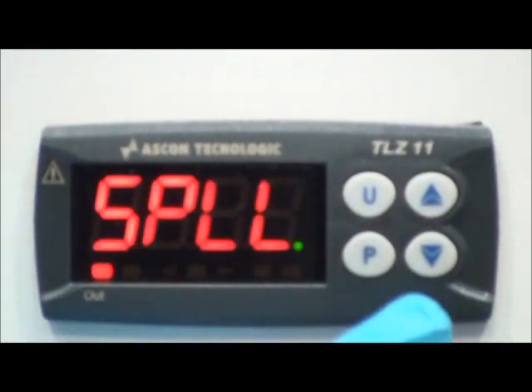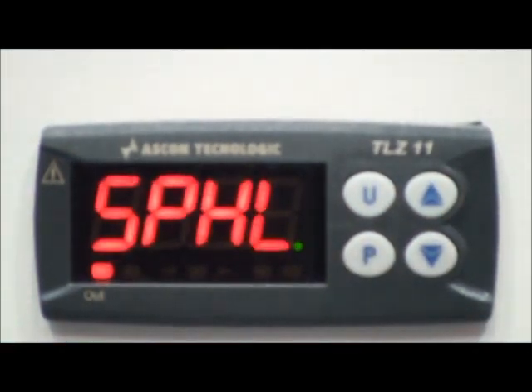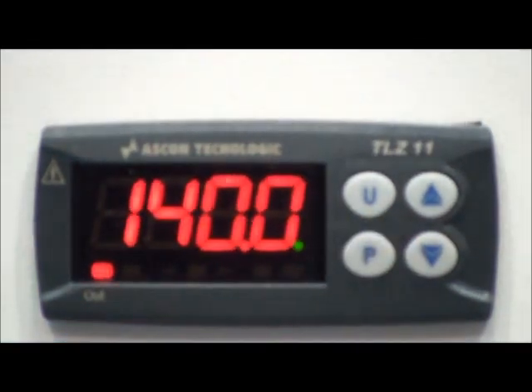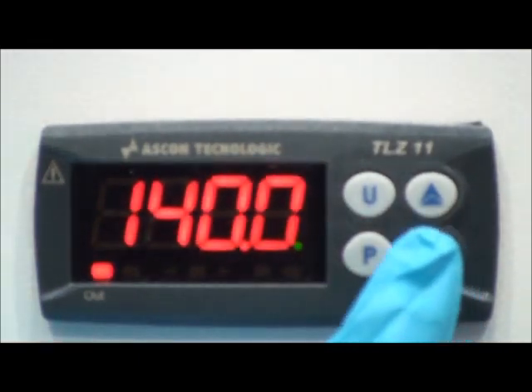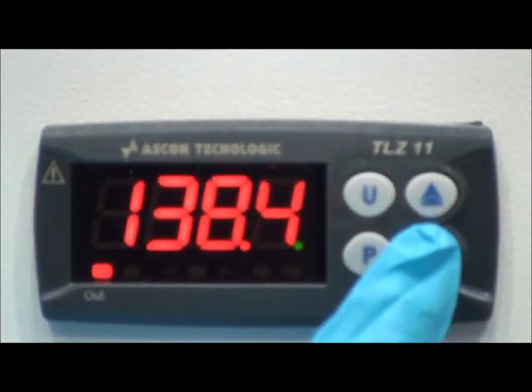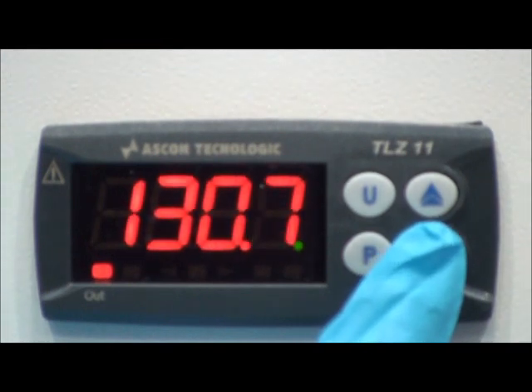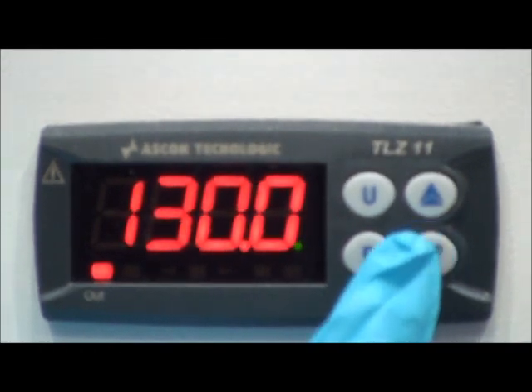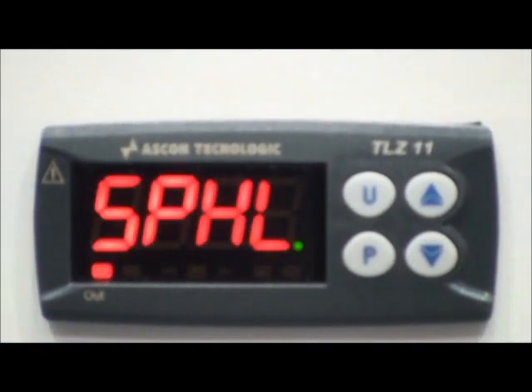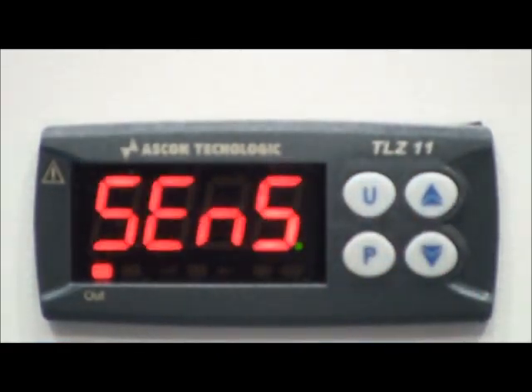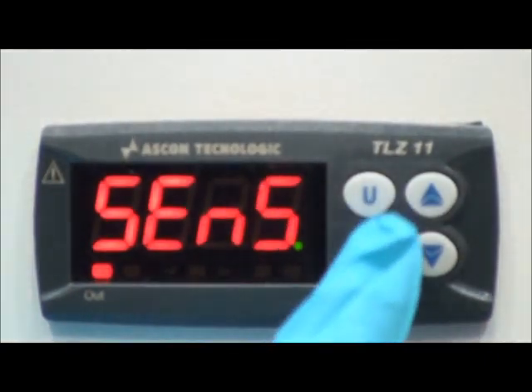Now you go onto the arrow key to move to the next parameter, which is a set point high limit. To access that again, you press P. At the moment it's set for 140, so we're going to lower that down to 130. And as you can see, it comes down by pressing the arrow keys. To accept that, you then press the P key. That's accepted. Now you move on to the next operation, which is the sense. The sense is preset and it should be on PTC, which it is, and you accept.